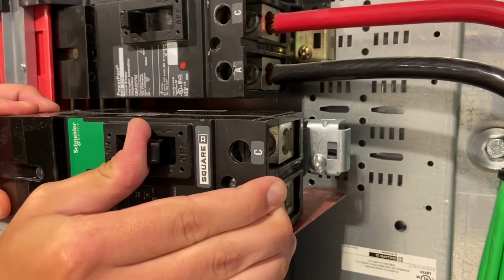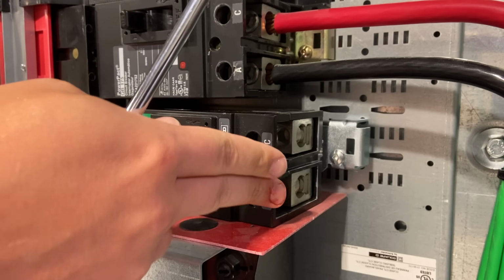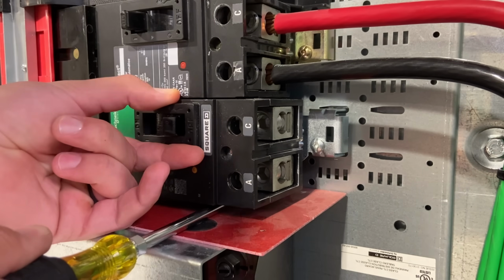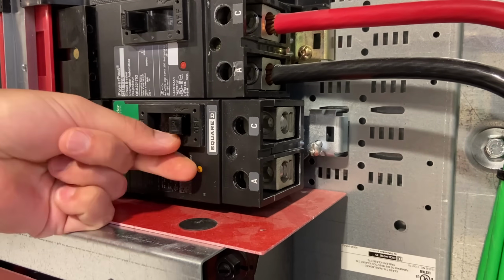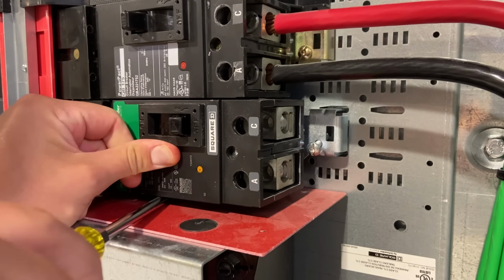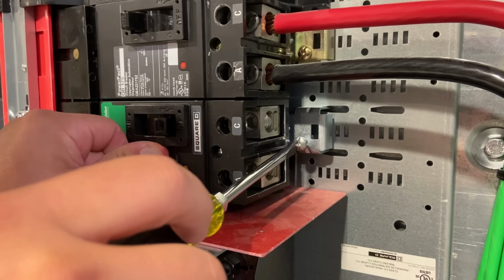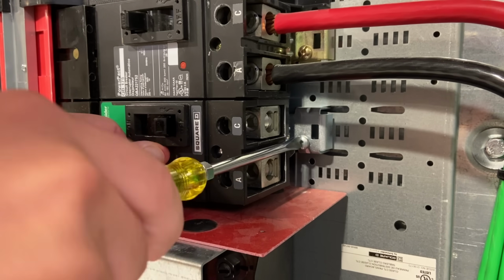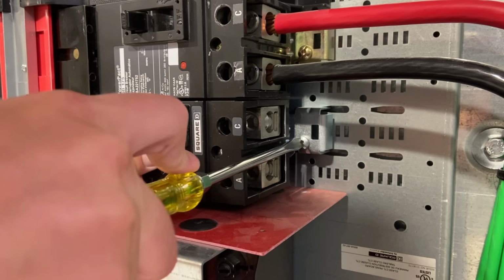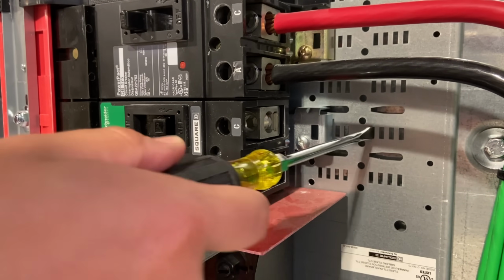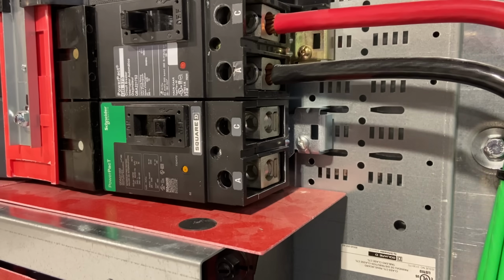Here I am installing that circuit breaker. I want to go ahead and turn it off first. If you've never put an I-line breaker in before, it's pretty simple. They've got these tabs on the back plate that you use to pry the breaker in with a screwdriver, and yes, that is actually how you're supposed to do it. You put that little screw in, make sure it's all the way on the bus bar, lining up with the other circuit breakers, make sure the screw lines up, and you're good to go. Those other tabs further out are for if you have a much larger breaker.